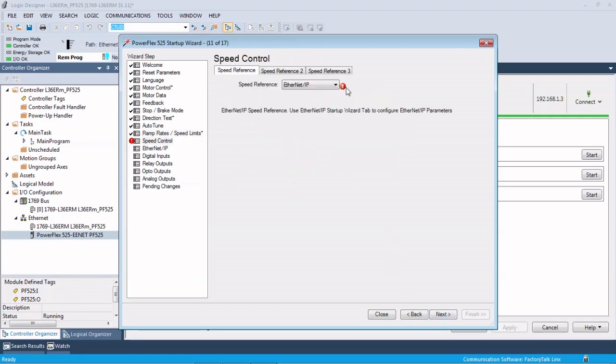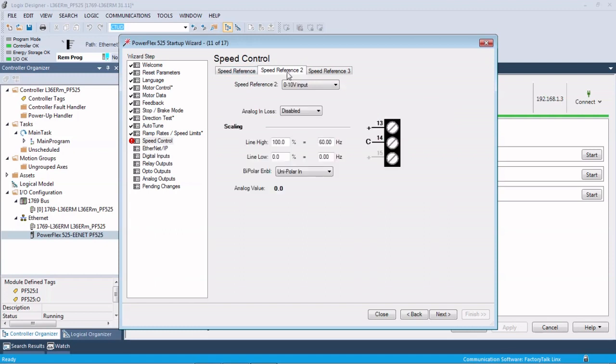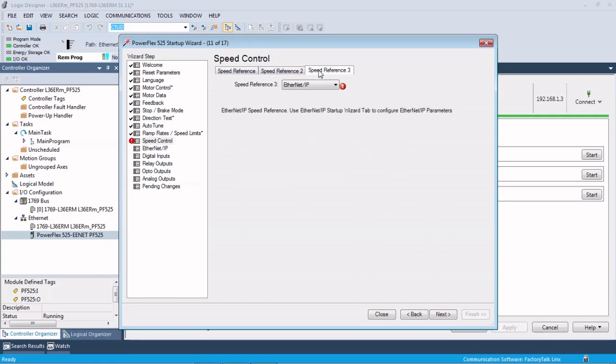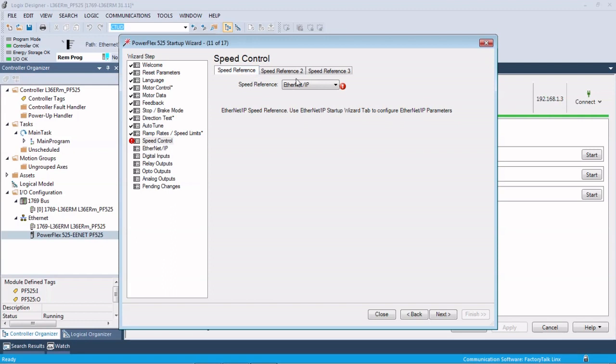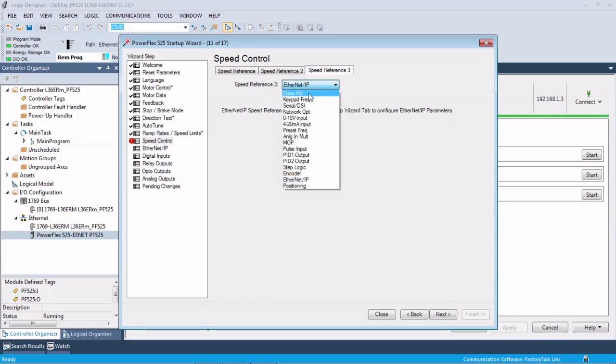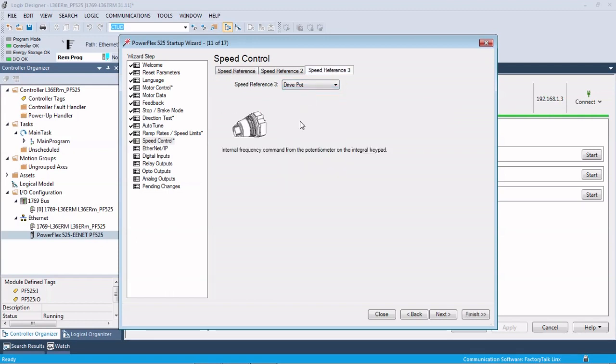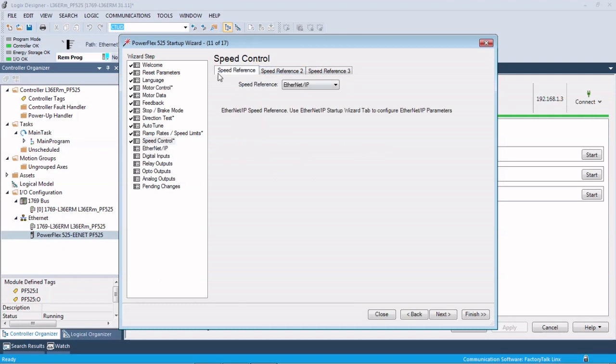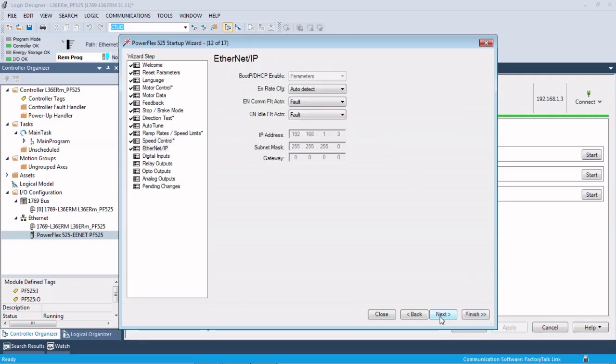Okay, so you see we've got an error here, and that's because we have Ethernet IP assigned to Speed Reference 1, and actually we have it assigned by default to Speed Reference 3. So it's giving us an error that they're both set to the same. To get rid of that error, we're just going to change Speed Reference 3 to the drive pot, and that gets rid of our error. Ethernet IP, this is what's set through the parameters, like I said before we started the process here. We got rid of the Boot-P and set it using the parameters.